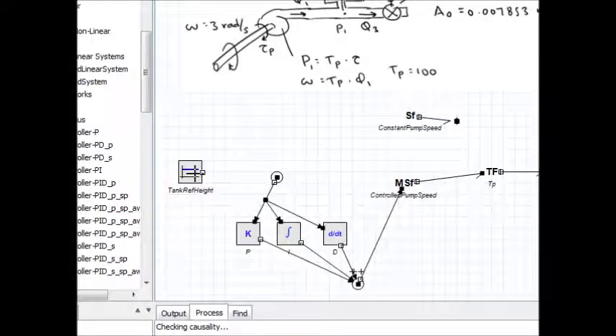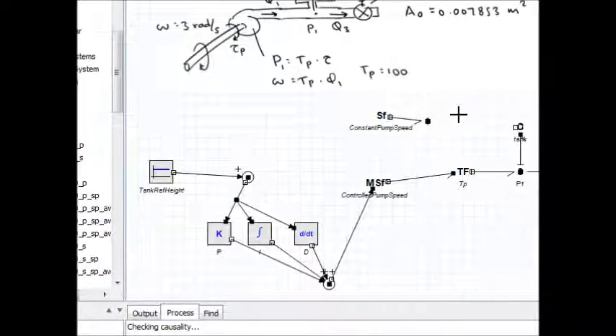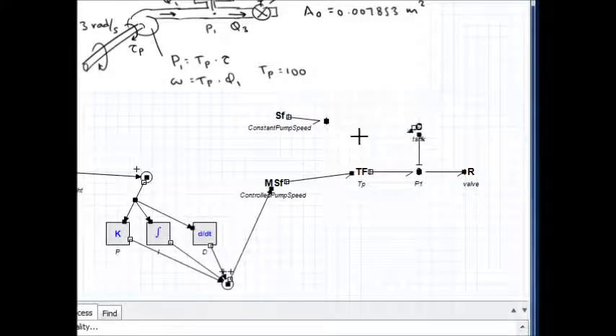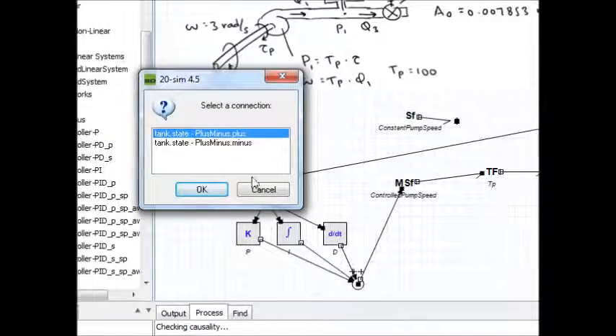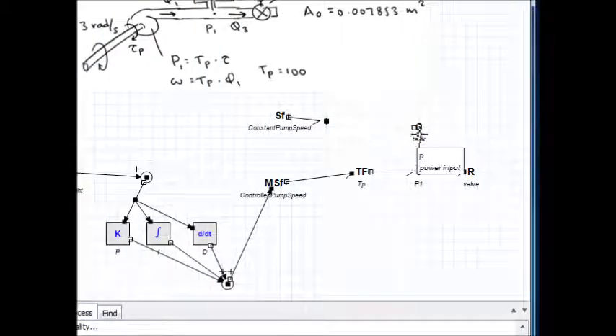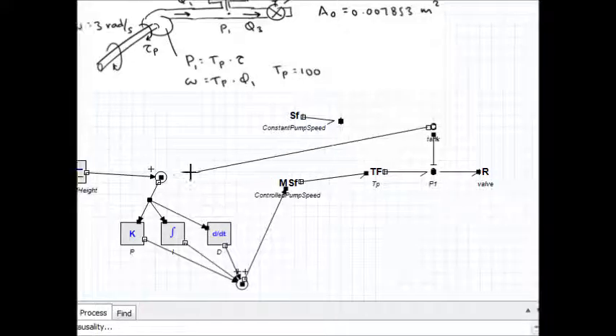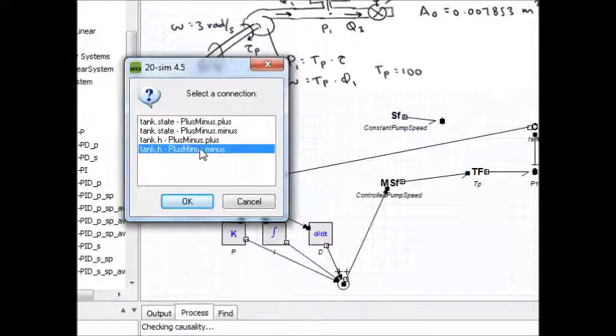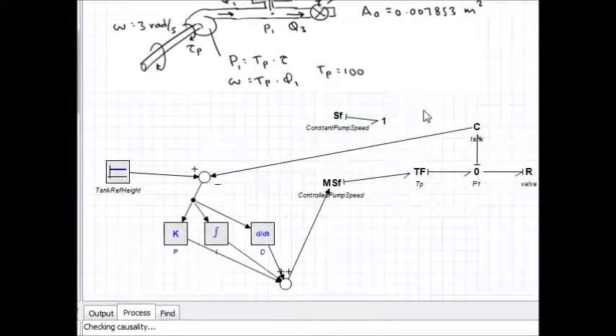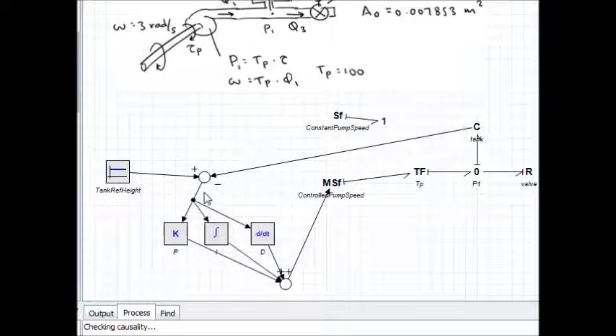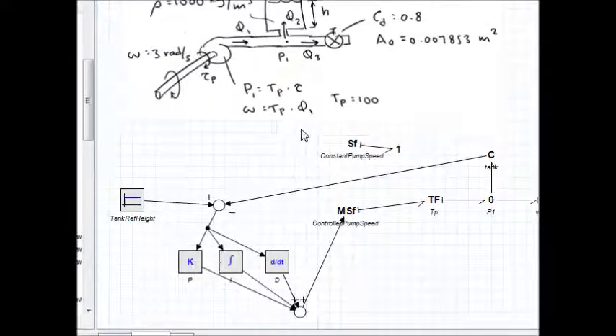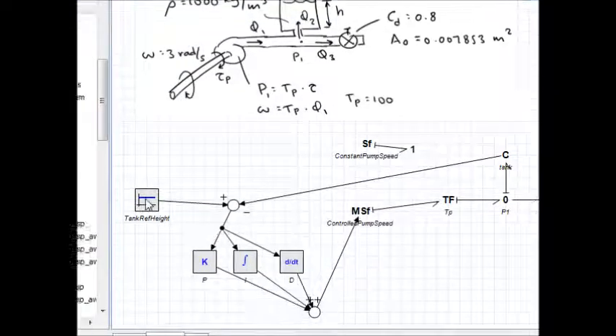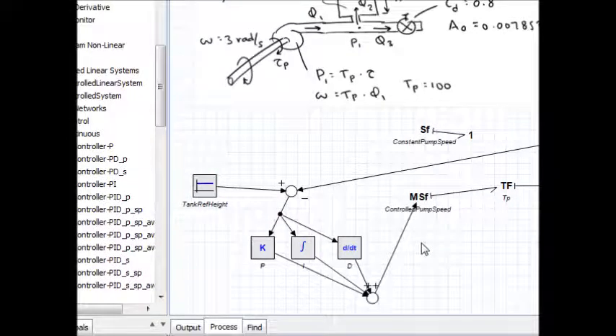I'm going to switch this around so that I have tank reference height going into the plus and the tank height going in as the minus. So let's try that. Now we're going to start off with an initial error signal which is positive, and we're going to have a positive pump speed.